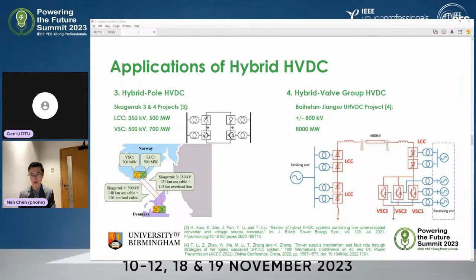And the fourth one is about the practice of the hybrid valve group HVDC. The best practice is the Baihetan Jiangsu ultra high voltage HVDC project, also with plus minus 800 kV and 8 gigawatt capability. You can see from the topology that the inverter side of the HVDC link consists of a 12 pulse LCC HVDC cascaded by 3 VSC HVDC in parallel.